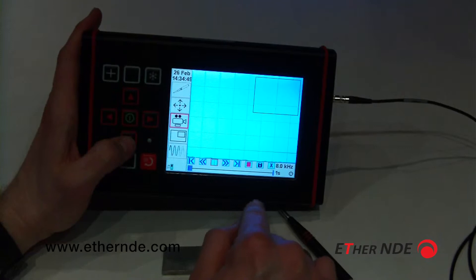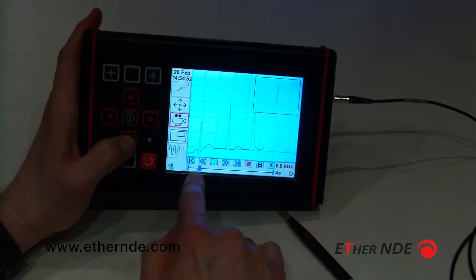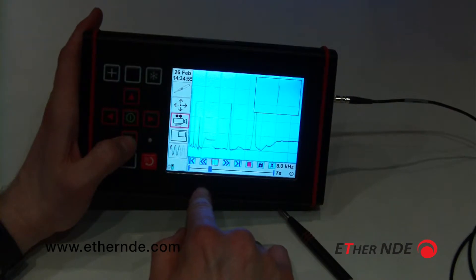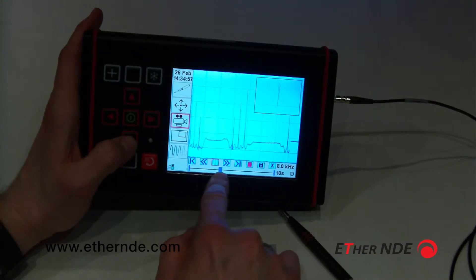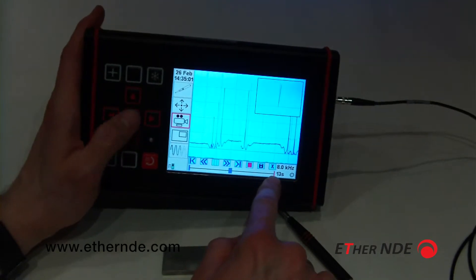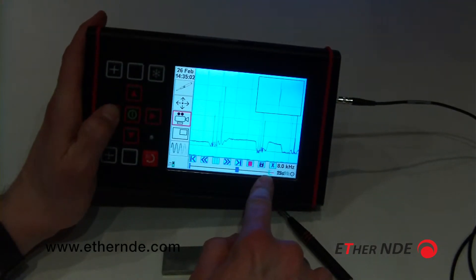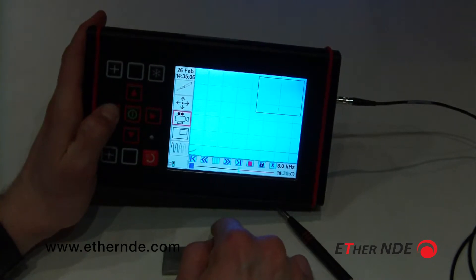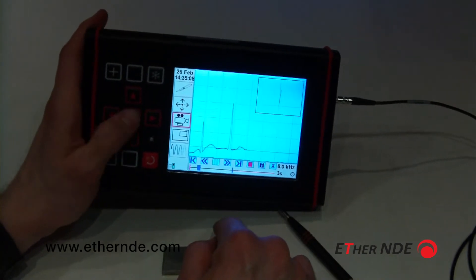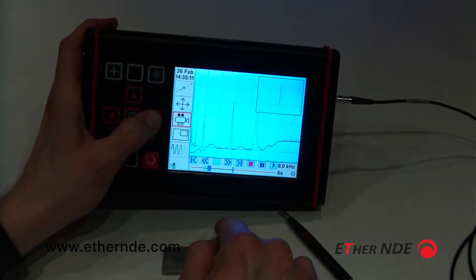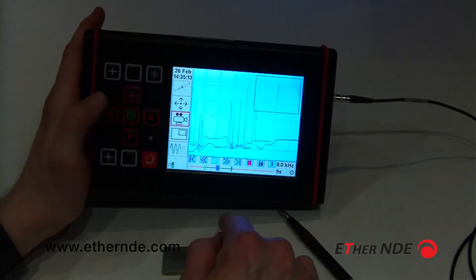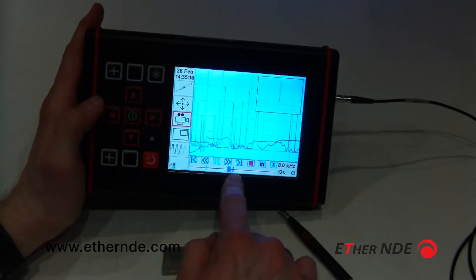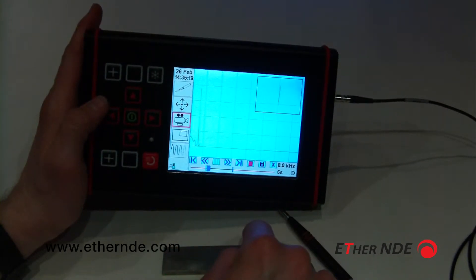There's a particular point we want to look at. We have a nice trace. Let's play a bit further. There's an interesting point around here. I can move the cursor to the stop bar and move it in. Into the start bar. Now only the data between these two points is going to be played back from the recording.